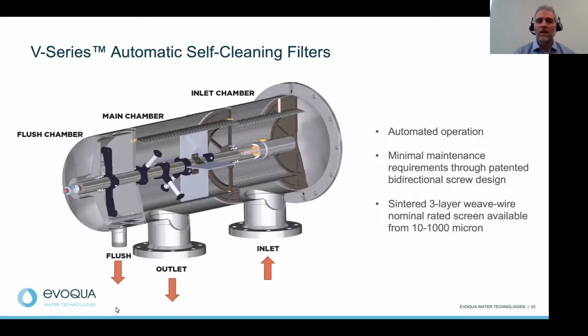As the flow enters into the main chamber or the center of the filter, that's where you find the fine screen. And the fine screen, Evoqua's fine screen, is something called a sintered 3-layer weave wire mesh screen. And this is a screen that's really high level capability of removing particulates at varying degrees. Water's passed through that fine screen. Solids are collected on the inside of that screen, flow out inside to out, and then out to the outlet on the bottom here. So that's filtration.